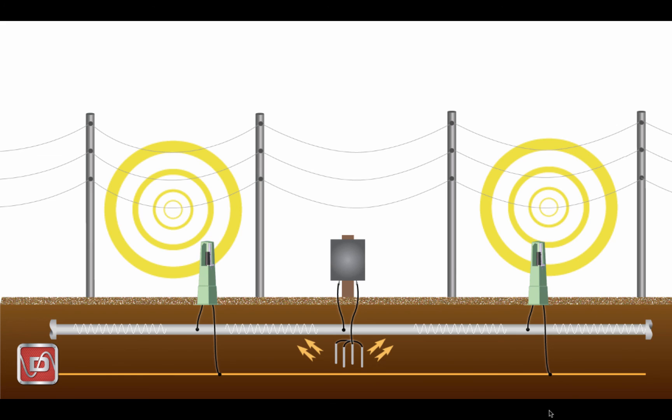If an AC fault and lightning event occurred, the device would temporarily switch to a completely shorted mode to provide worker protection, yet the cathodic protection system will continue to operate as if there is no safety bonding to ground.